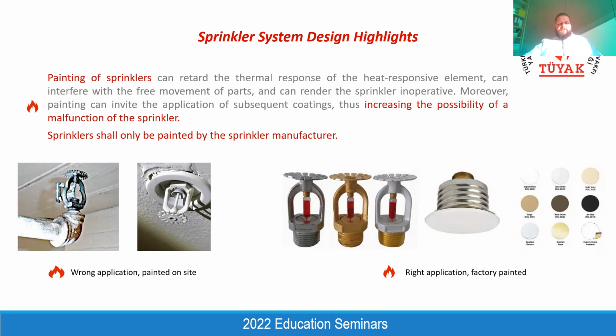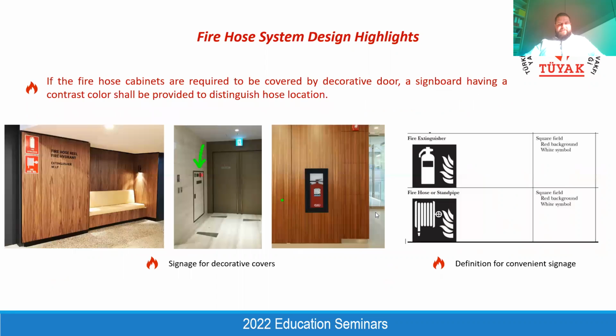Otherwise, if you require the painters to paint the sprinklers on site, when the fire check comes, they will require you to renew these sprinkler heads, and all of these sprinklers will go to the rubbish, and it will cause loss of money and also loss of time due to the waiting for brand new sprinkler heads.